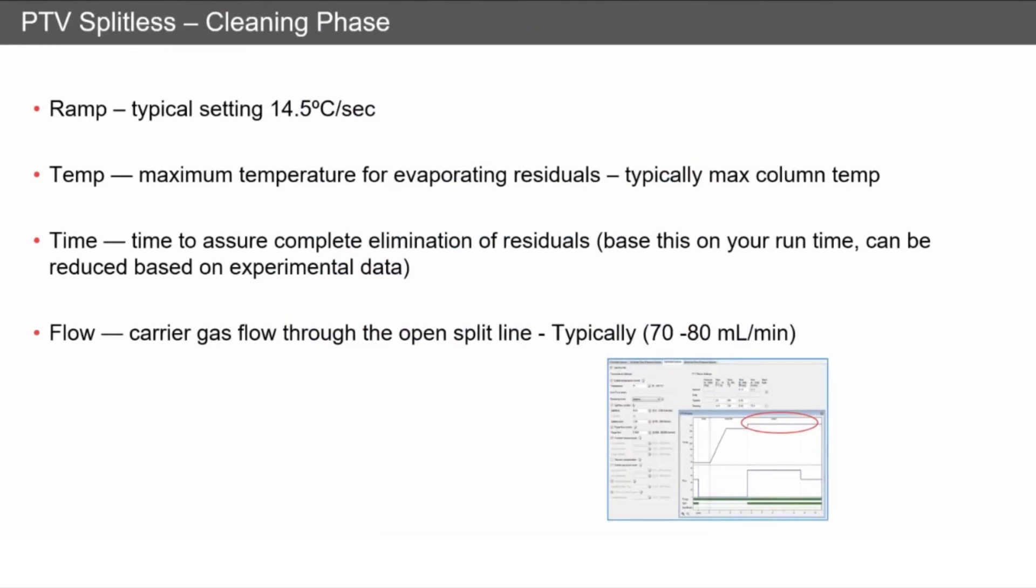This is the amount of time to assure complete elimination of the residuals, and I would base this on your runtime. So if your runtime is 15 minutes, you can easily have a 10-minute cleaning time because the inlet will be cooled down very quickly and be ready for your next injection.